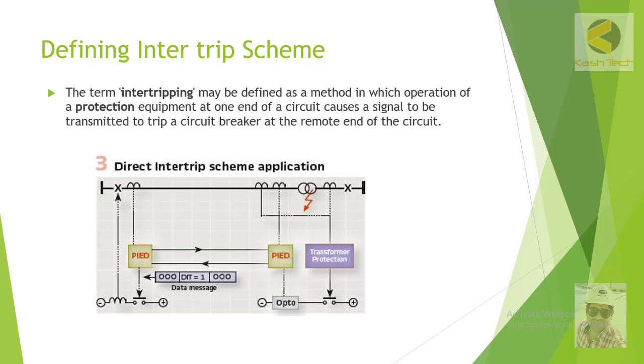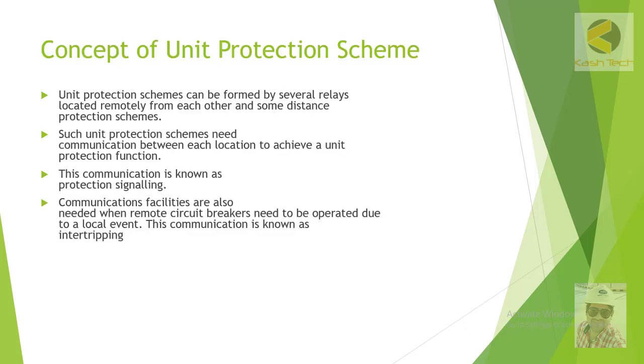This is basically an example of transfer tripping, which can occur in the case of a radial feeder among other applications. Unit protection schemes can be formed by several relays located remotely from each other. Some distance protection schemes need communication between each location to achieve a unit protection function — this communication is known as protection signaling.